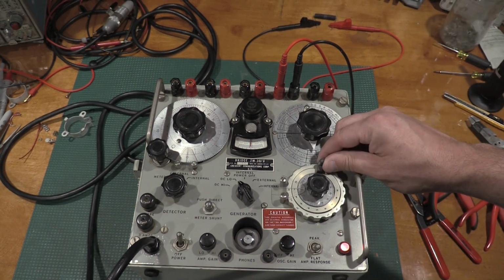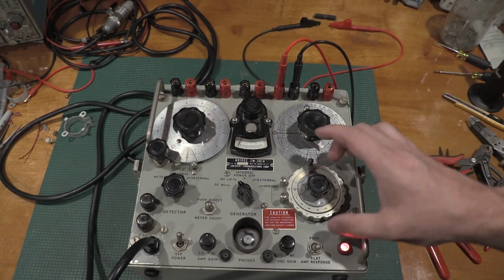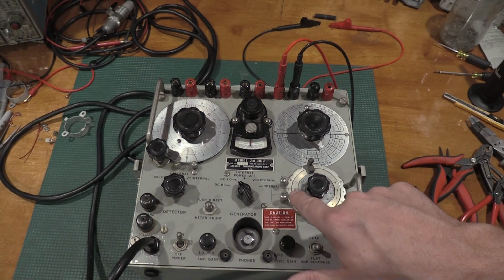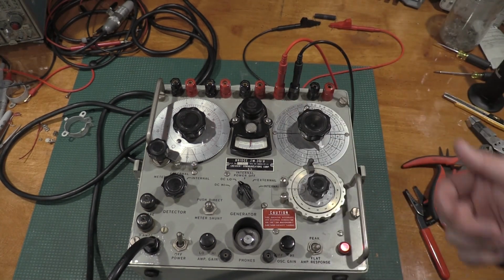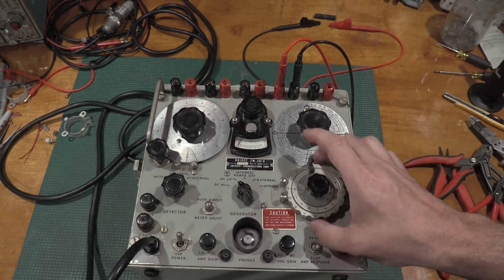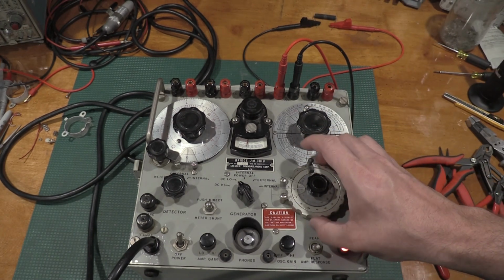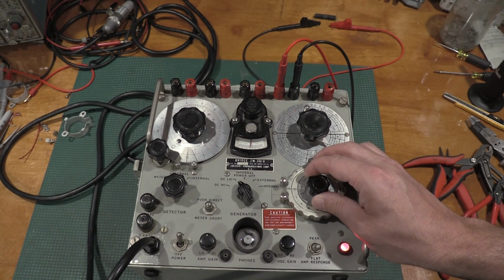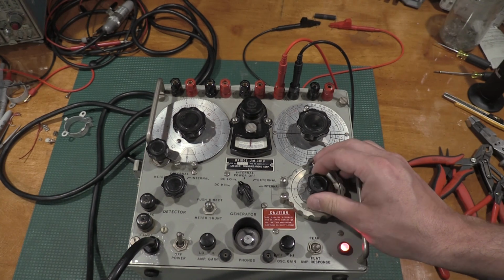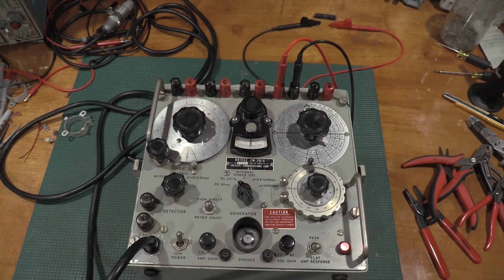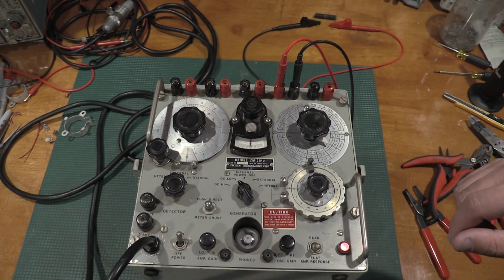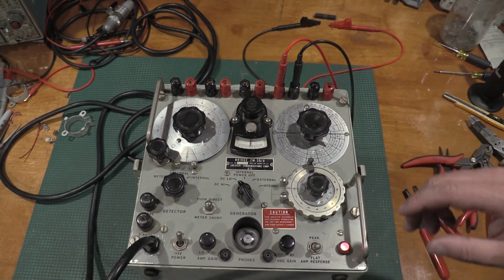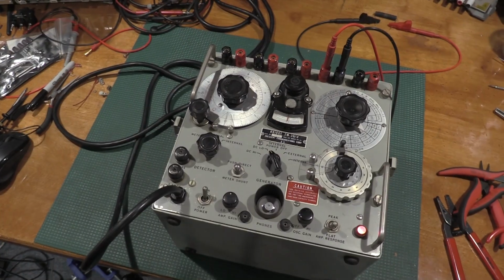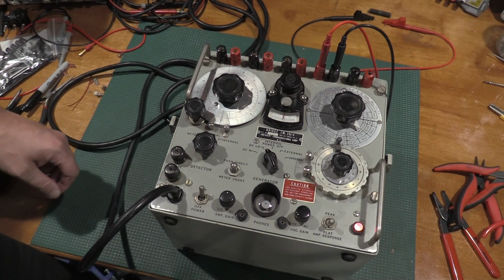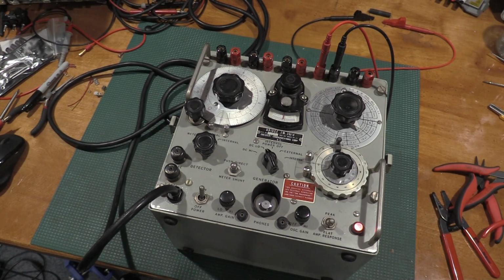If I go to the 10 ohm range, I click this over to 1.00 on the 10 ohm range is 10 ohms. If I go to the 1 ohm range, if I go to 10, and a bit and some change, we can get the bridge to balance. So, I had my dial settings set a little wonky, and that is why it was mildly confusing at first. So for now, everything is in balance and working, and I'm going to let this sit on the bench and do some burn-in testing, make sure it works for the long run, and is ready to go.